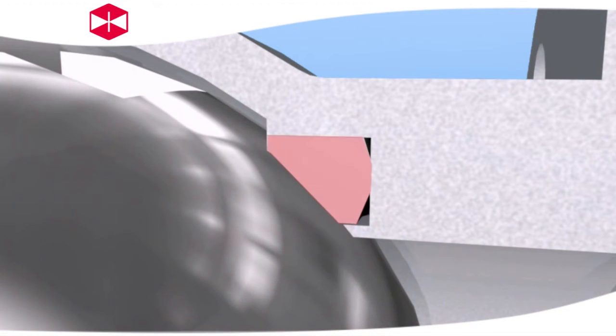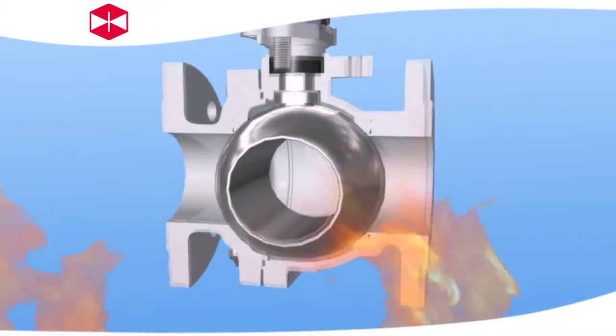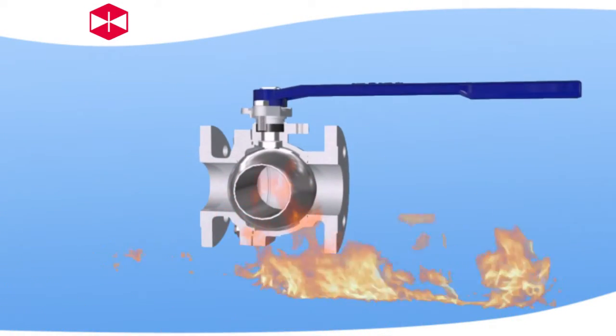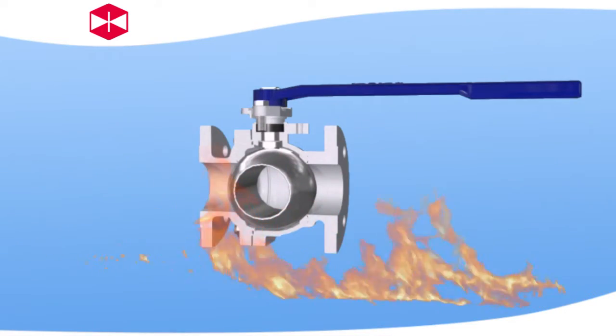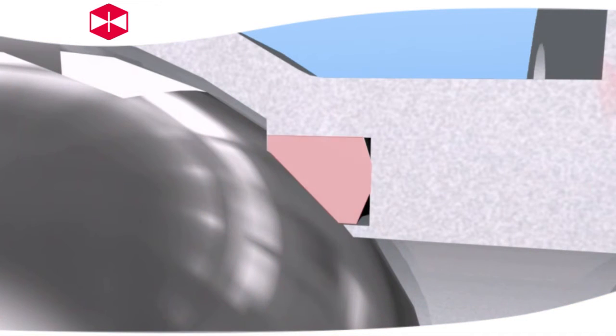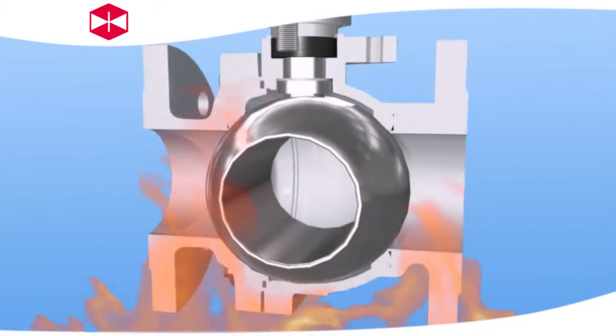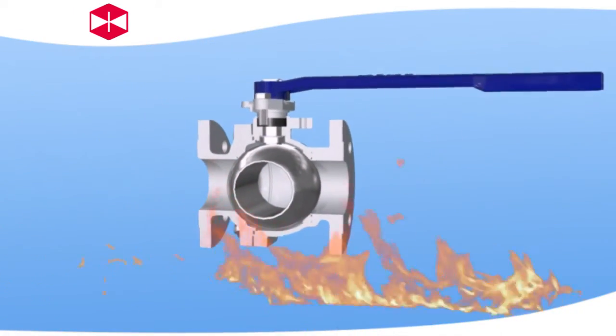The fire protection structure function is to prevent the medium from much leaking. The ball valves made by VARC are provided with a metal fire protection layer on the seat face. Once the seal is burned, the ball will directly contact with the metal face from the body, thus preventing medium from leaking out. The valve fire protection structure design is according to API 607-API 6FA.